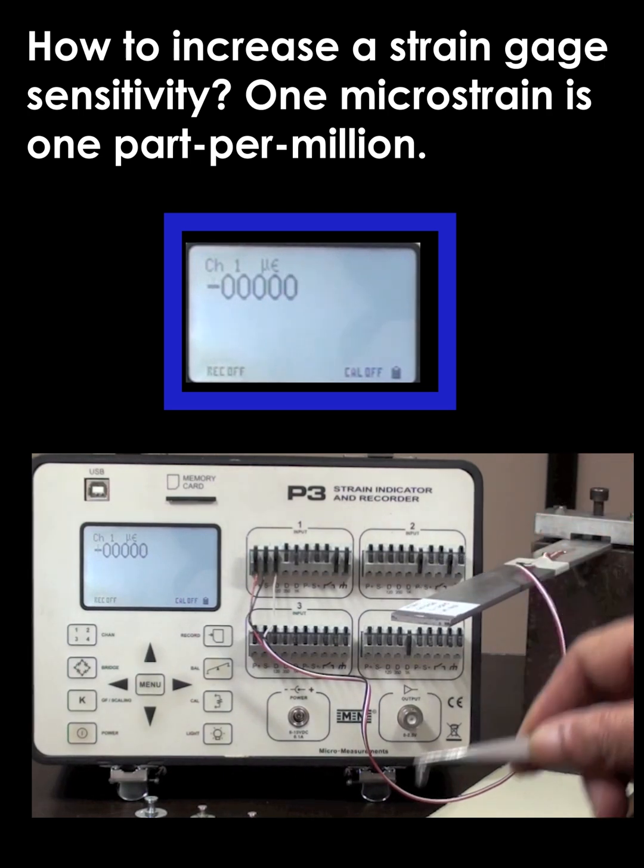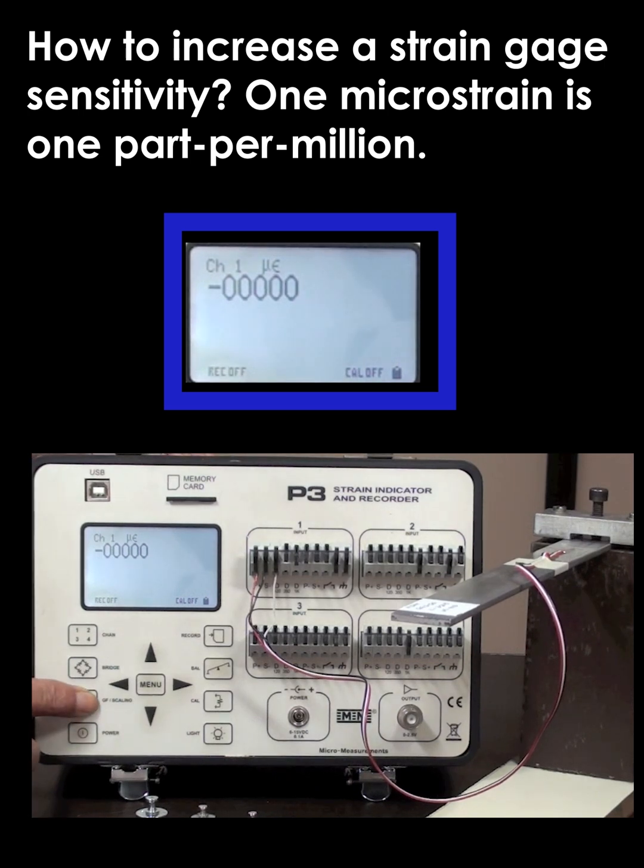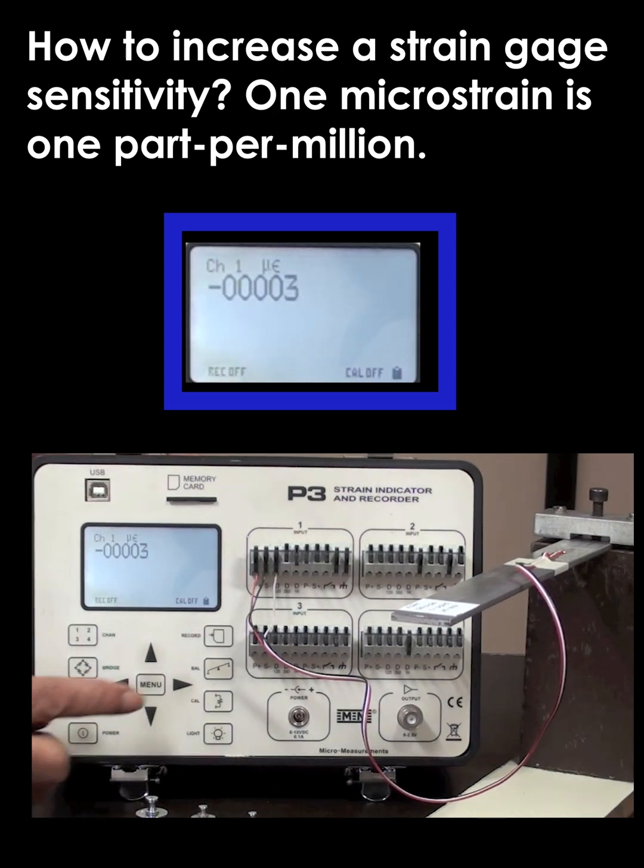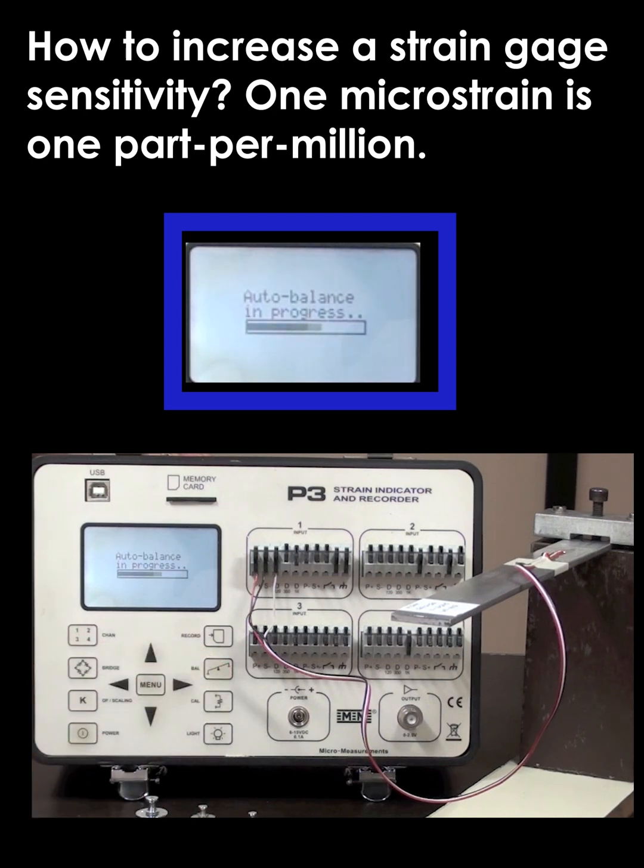Now one of the things you can do with a P3 is dial in the gauge factor. Remember we dialed it in to 2.120, but what we're going to do now is shift it by one digit—so instead of two point one two, it's going to be point two one two. Effectively, what that does is it gives us ten times the amount of resolution, so we'll balance it again to zero.